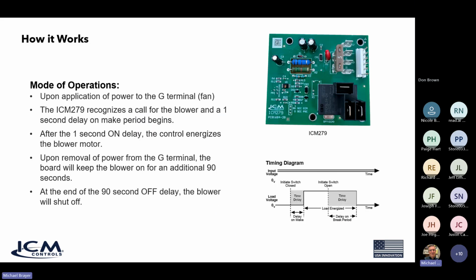So how does it work? The board gets a call from the G signal, G terminal, or the fan. The board recognizes that, pauses for 1 second, before it delivers the make. After 1 second, it energizes the blower motor. The blower motor continues to run for the duration of the cycle until all of a sudden there's no power coming from the G terminal, usually meaning the thermostat has reached its desired temperature and it shuts off. And then the blower stays on for 90 seconds after that off signal, to purge that ductwork from that heated or cooled air. And the right is a timing diagram. That timing diagram also is included in our installation manual, in case you should ever need it.